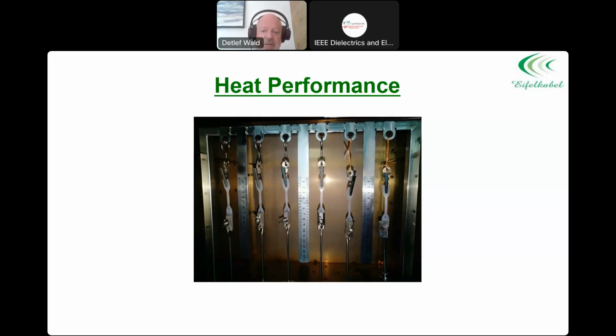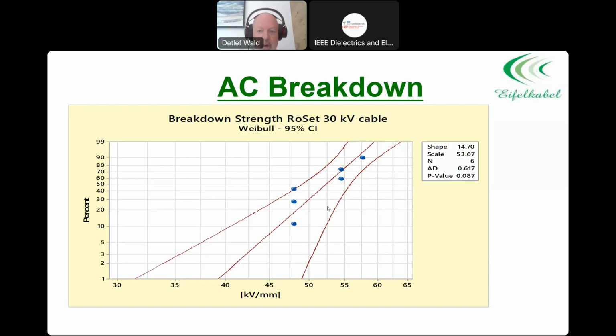The elongation of polypropylene and XLPE were in the same range over time. The surprising thing, surprising even for me, was that the polypropylene even moved back when we removed the weight, so the elongation was not permanent. Why? I still don't understand. Looking now more at cable data, RoSet is a commercial name by one of the machinery suppliers. Cable data are showing the same electrical properties of polypropylene as with XLPE.